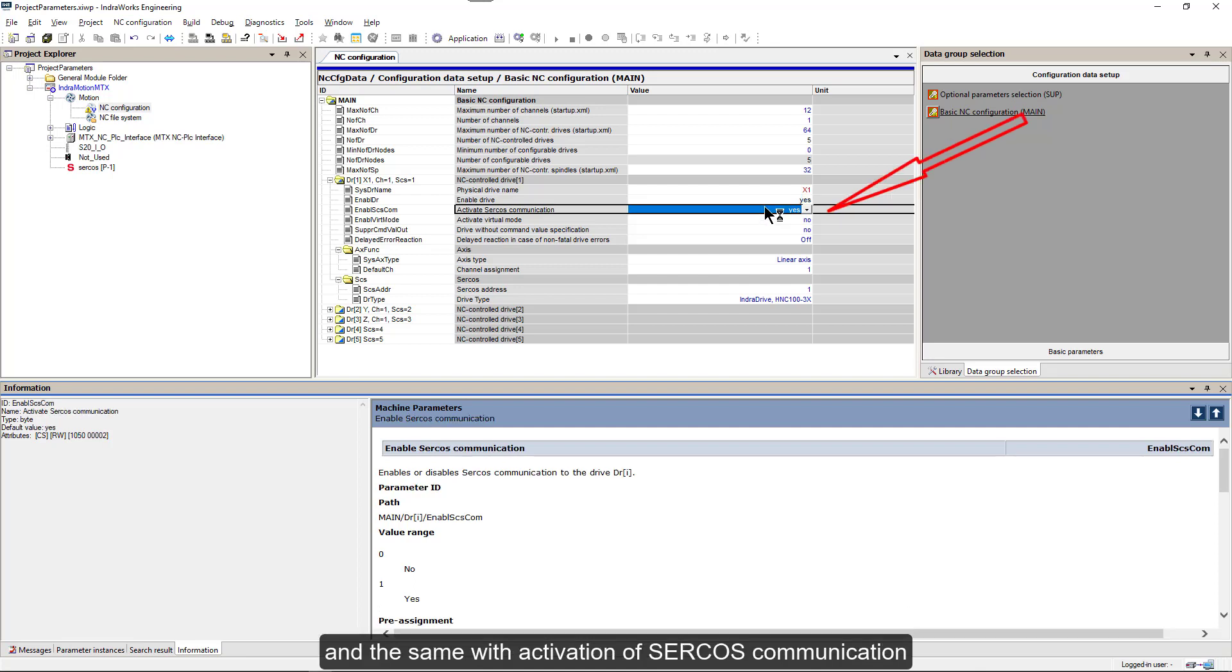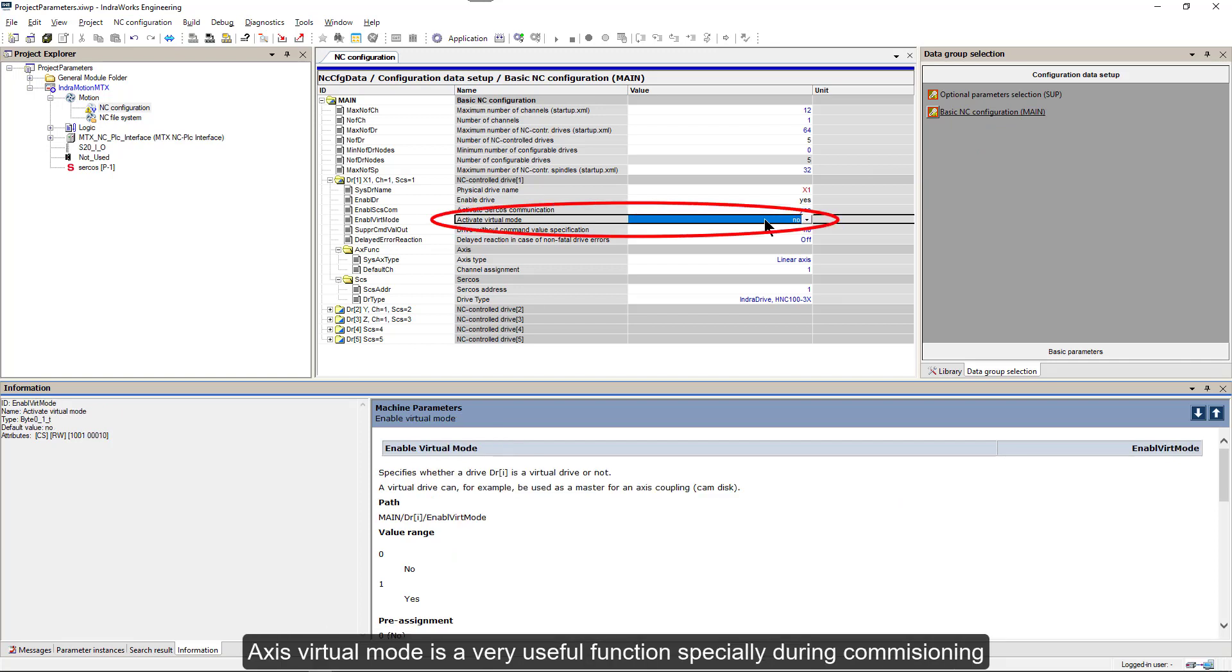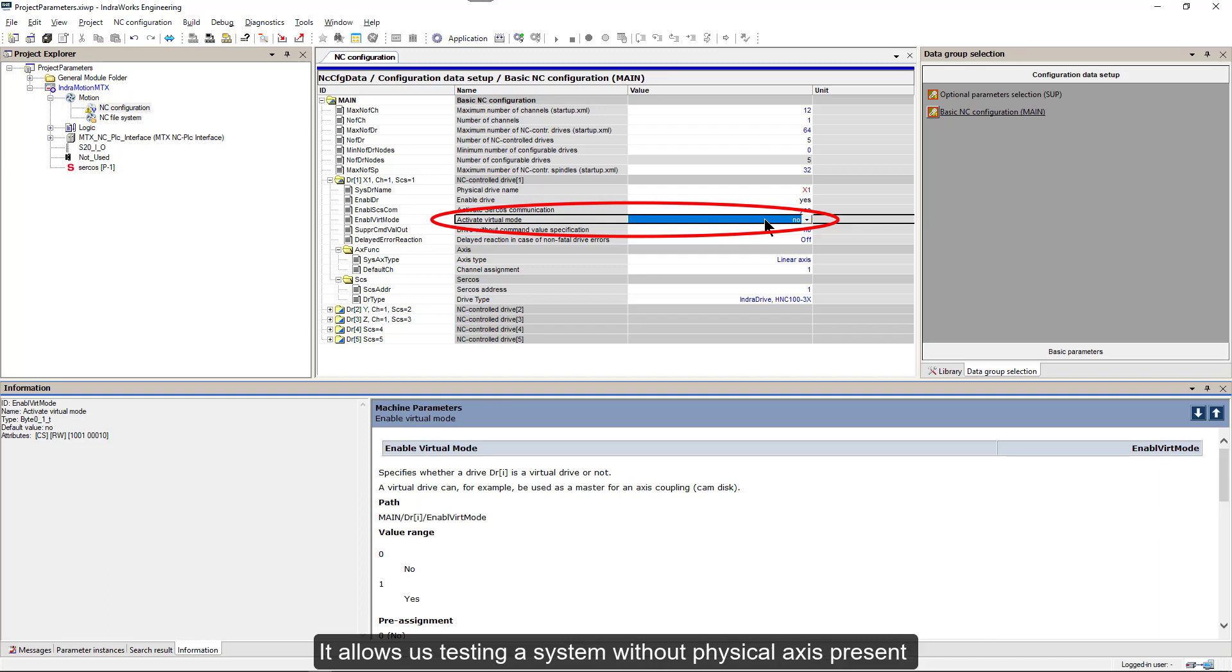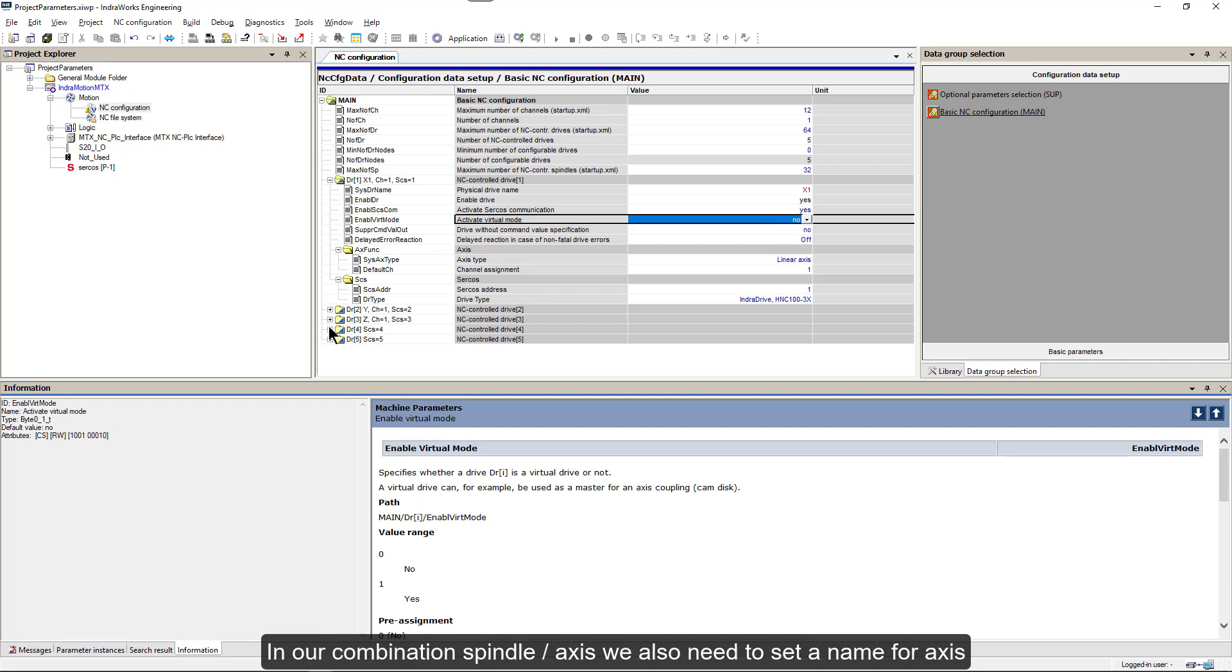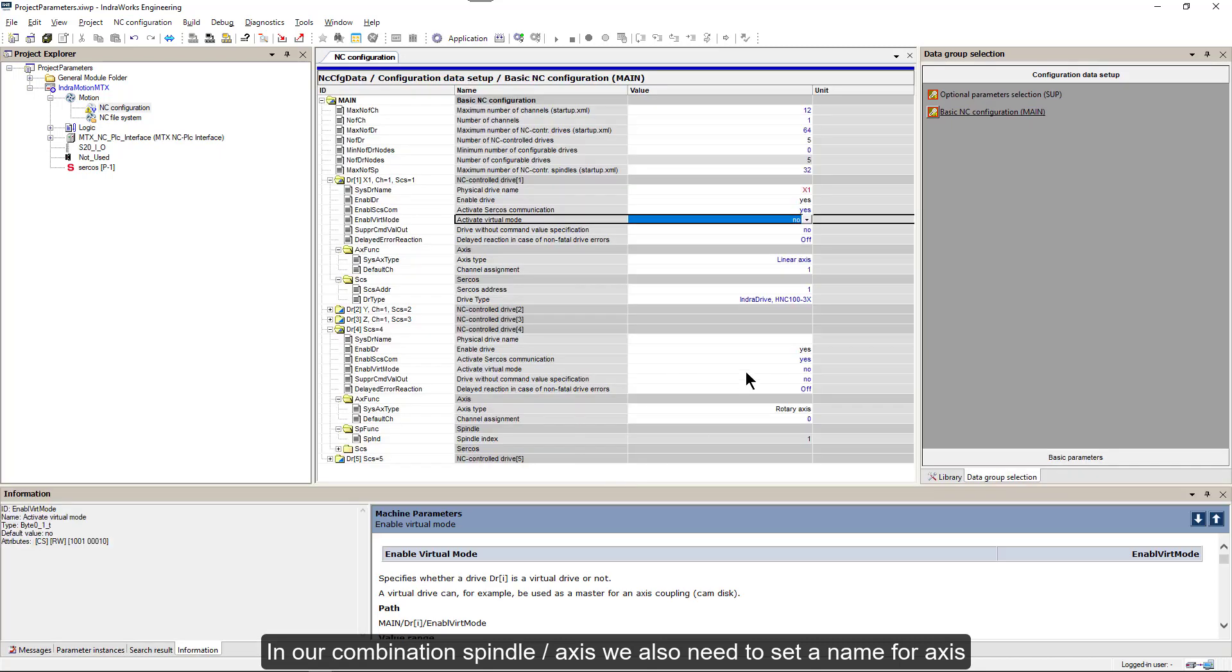And that means parameter was modified but not activated. Next parameter enable drive will leave as yes. And the same with activation of SERCOS communication. Axis virtual mode is a very useful function, especially during commissioning. It allows us testing a system without physical Axis present. In our combination spindle Axis, we also need to set a name for the Axis.